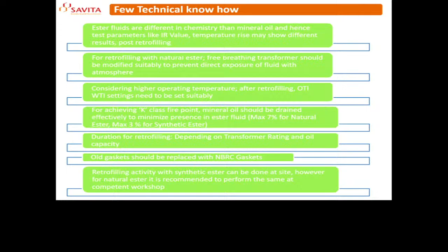Then your gasket should be removed and changed with nitrile bonded gaskets. Also, ester fluids have higher viscosity, so your OT and WT settings have to be checked after retrofilling.